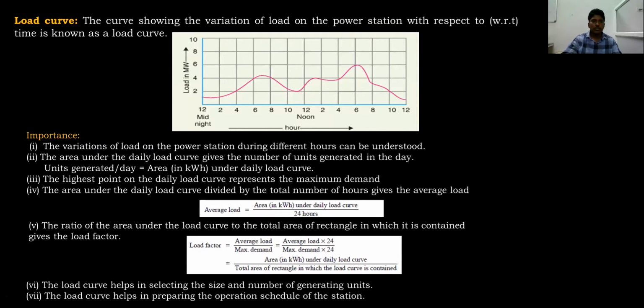And load curves. It is very, very important to know what is the load curve and load duration curve. Load curve is the curve drawn between load and time in a day. Here load is in megawatts and time is in hours. Therefore, at 12 o'clock you have less than 2, and during 6 p.m. you have a maximum demand here which gives you 6 megawatts out of a 10 megawatt plant. This is a 10 megawatt plant load curve.